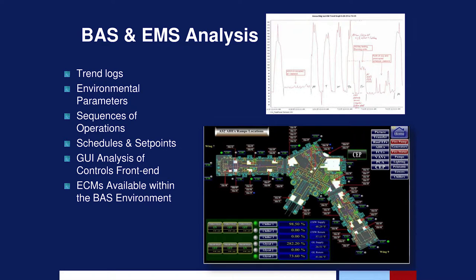Are they really maximizing the benefit of that control system? Does it have all the information that ought to be in a one-stop shop? Things like equipment nameplate data, make, model, serial number, refrigerant charge, amp draw, that type of stuff you see on the equipment could be on the equipment graphics as well, so a new service tech doesn't need to hunt for that information anywhere. Same with factory service manuals, bill of materials, and as-built documents. These are all suggestions to be rolled in and implemented into the building automation system.